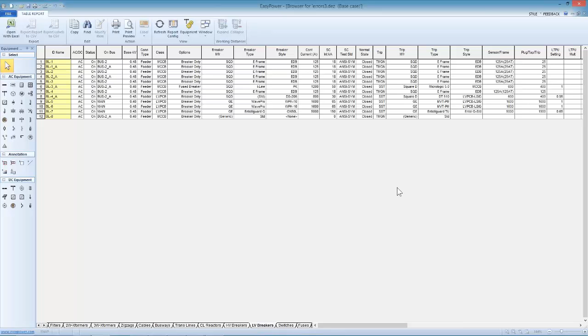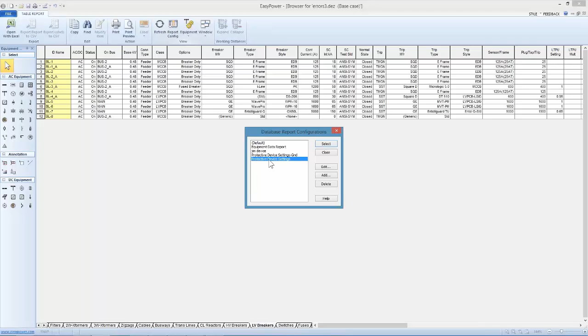The other one is fairly along the same lines as far as useful feedback and glancing at what's going on at the 3,000-foot level. I've selected the low voltage breakers. I'm going to look at my equipment protective device settings, select that display, and now I can see, at one fell swoop, I have a lot of molded case circuit breakers, which I wouldn't expect to see long-term pickup settings on, but on my low voltage power breakers, I would expect to see entries in these areas. Now that may or may not be an error, but I want to verify that we're using the right settings before I go any further.